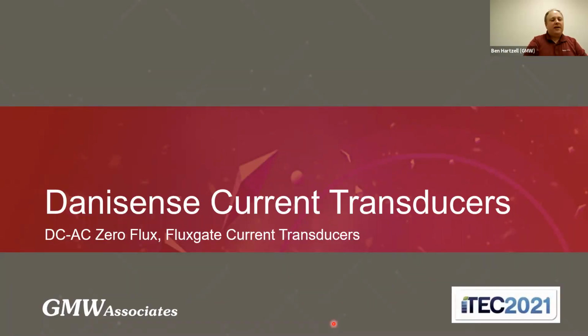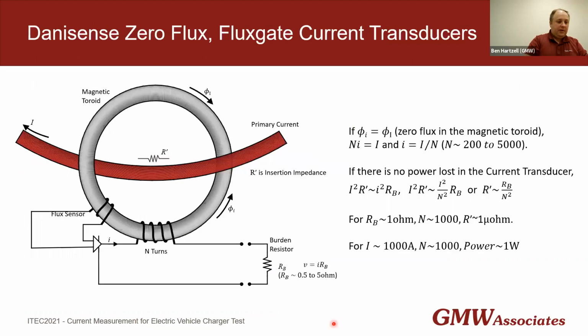Next, I want to look at the Danisense Zero-flux Fluxgate current transducers. These are DC and AC current probes. And zero-flux current transducers, as the name implies, operate on the principle of keeping the flux within the magnetic core at zero, using a Fluxgate as the magnetic field sensor. The current transducer is a closed-loop transducer.